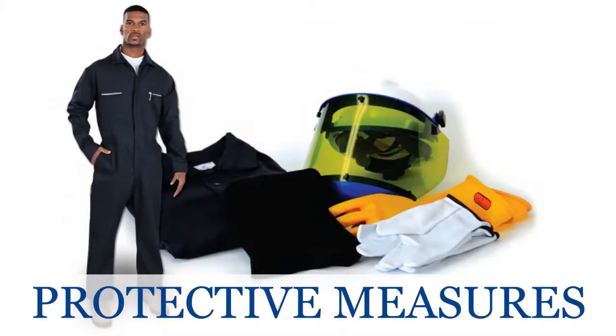And while you're testing for absence of voltage, you're actually putting yourself at risk of an arc flash. So the PPE is so important, and it needs to be included in every single job. And then from there, if there are engineering controls or administrative controls or anything else that you can add to that procedure or that job, well, that's fantastic. But just going through it on a day-to-day basis, that's the thought process that an electrical worker needs to take. And 99% of the time the answer to the whole question is, well, it's PPE.